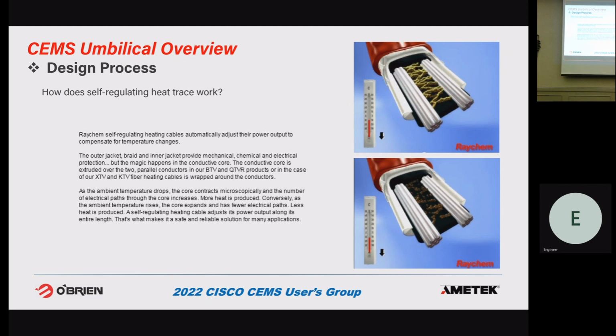So back to what I was saying, self-regulating tracer, what that temperature window, where it's going to operate in, depends on your ambient temperatures, how many tubes and what sizes they are, voltage, a lot of factors. The greater your ambient temperatures, coldest day of the year to hottest day of the year, the bigger that window of operation is going to be. So if we were designing a bundle to maintain 150F, we're going to shoot for 150F on that coldest day of the year. And on the hottest day of the year, anything above that, it's going to be above that. And so maybe it'll operate between 150F and 200F.